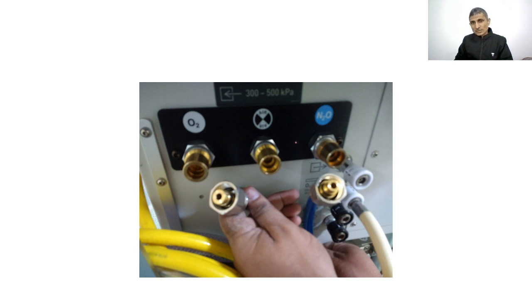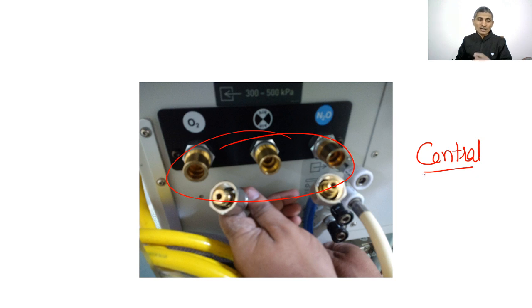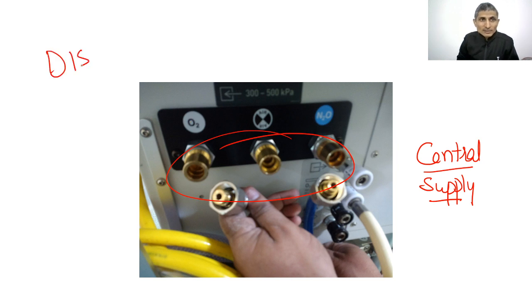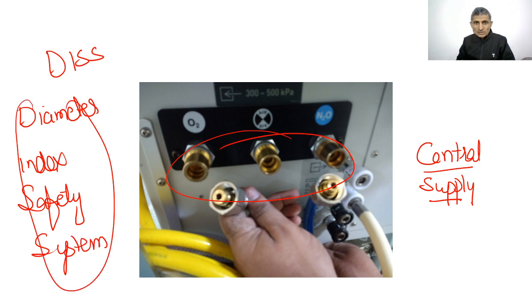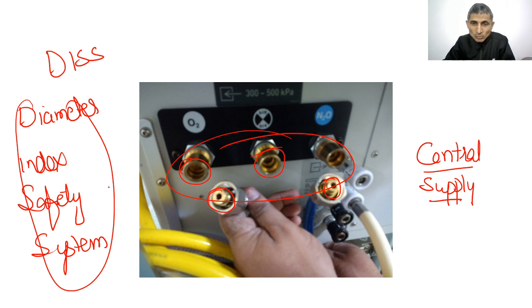The pin index safety system prevents wrong attachment of cylinders. For central supply pipelines, the diameter index safety system (DISS) is used — oxygen, nitrous oxide, etc. have different diameter connectors so the wrong gas cannot be attached to the wrong port. DISS prevents wrong attachment of central supply, while pin index prevents wrong attachment of cylinders only.